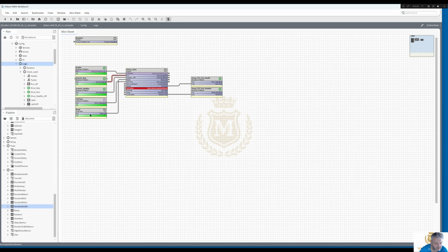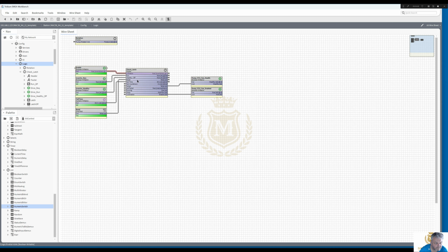Now we've got the alarm there. Let me just reset that. We'll go through that in a minute. And actions, emergency inactive, so we're not giving it an enable signal. Again, we've got manual run because someone is running that inverter manually, and this countdown is counting down the 30 seconds, and then once the 30 seconds, like you've just previously seen, we will go into fault.